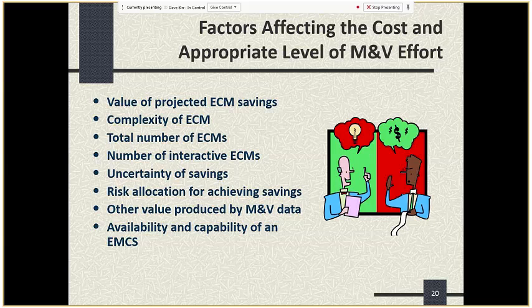The other thing you have to pay attention to is how much the ECMs interact with each other. In this case, when you put in LED lighting and replace fluorescent lighting, it turns out LED lighting has a much lower thermal waste heat output, so you take a lot of load off the chillers in zones that are cooled. Those savings are actually substantial. In a different climate zone with a significant heat load, that might not really help you, because even though you'd get savings from reducing the cooling load from waste heat from lights, you'd pay a penalty to the extent those lights were contributing free heat to your heating load in parts of the year. But in Hawaii, that's a non-issue because you don't really have a heating load to speak of. So LED lights here are almost a perfect application because they pretty much just reduce your chiller load all day long, all year long.